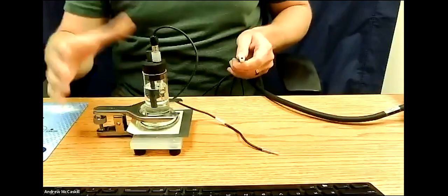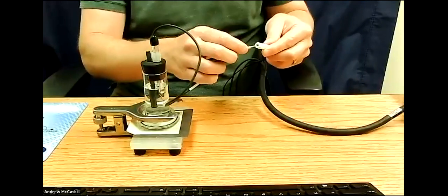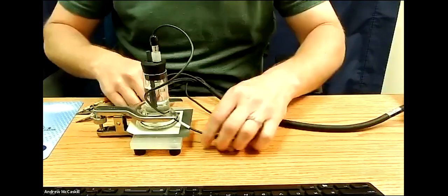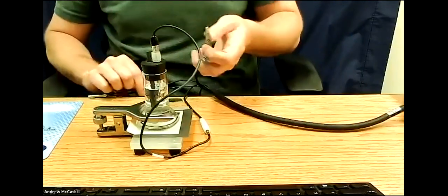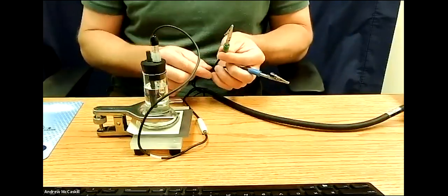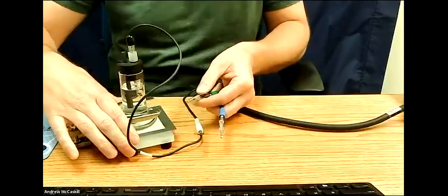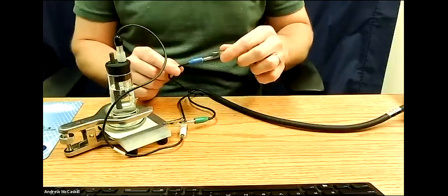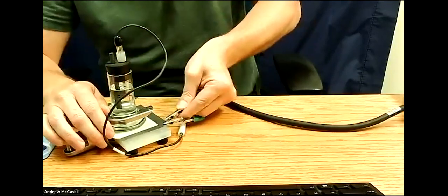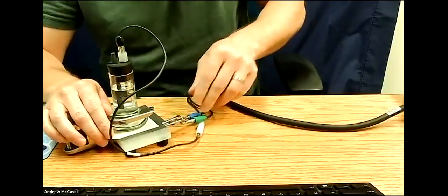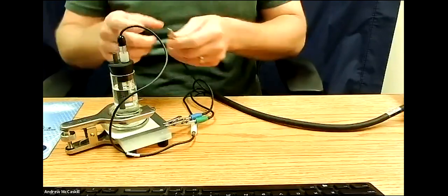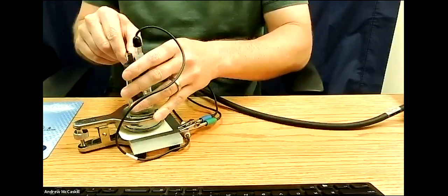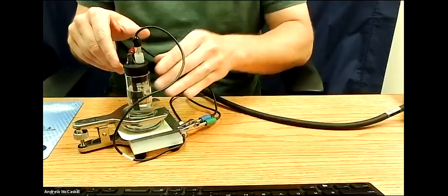So in terms of connections for our cables, this white lead will accept the plug for the reference electrode. You have your green current carrying cable that you're going to connect to your working electrode, which is going to be the sample. Same with your working sense cable. That's also going to be connected here to our working electrode, which is our sample. And then we only have left the red counter electrode, which I'm going to connect here to the graphite rod.